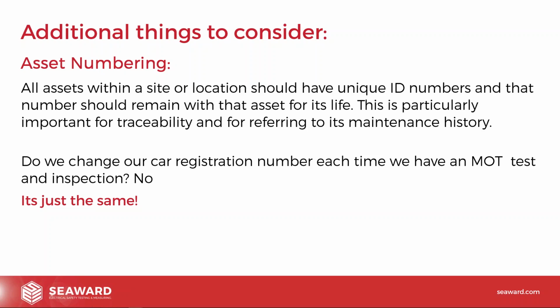And similarly the other way around, if you've got a piece of equipment that has failed several times, you need to reduce the test interval to make sure you're picking up the faults as and when they happen. So again, it's important to have that history there. And as Paul's put in there, do we change our car registration number each time we have an MOT? Obviously we don't. So it's just making sure that we've got that traceability, and we can demonstrate that we have been maintaining that equipment over time.